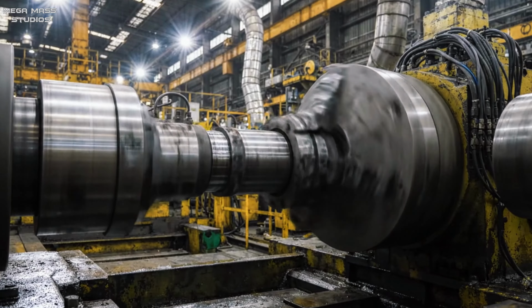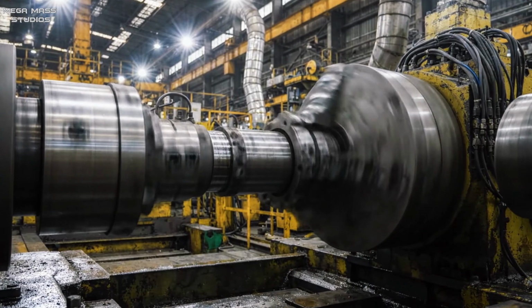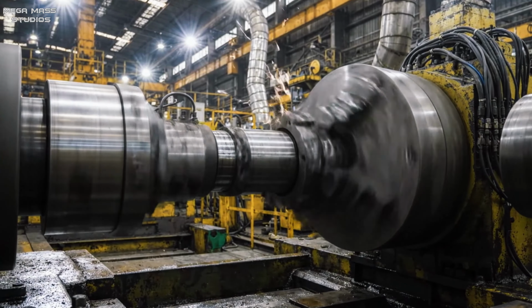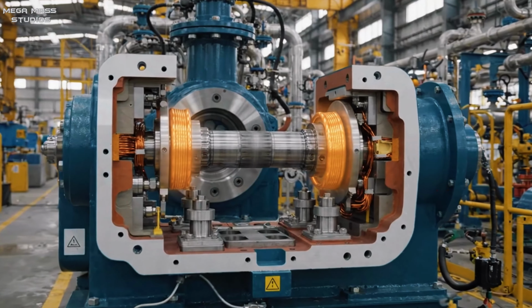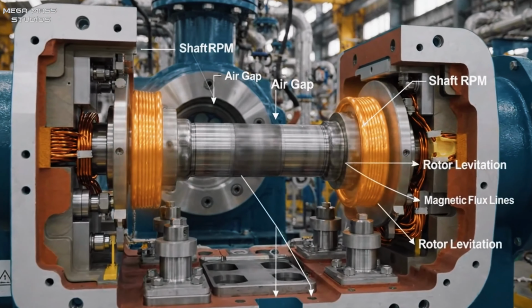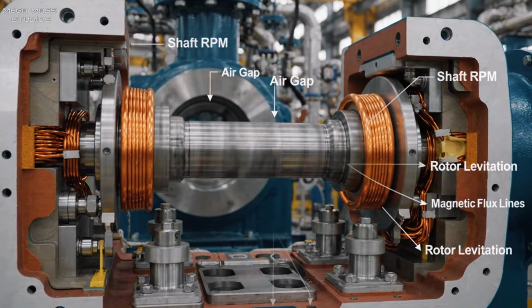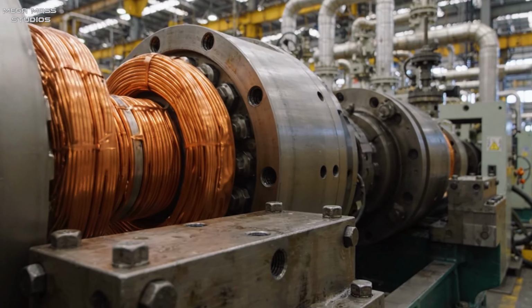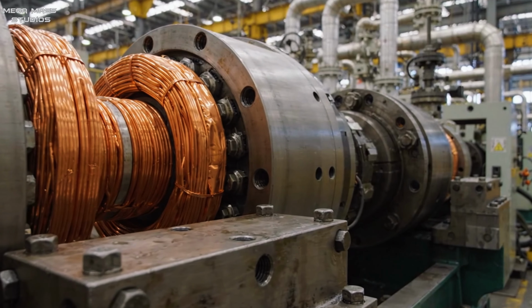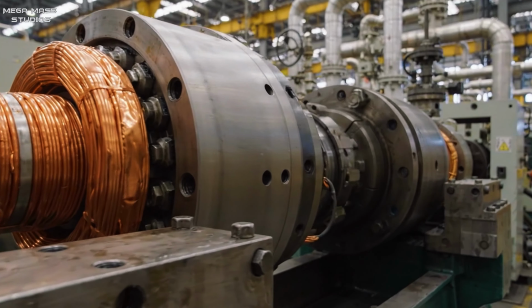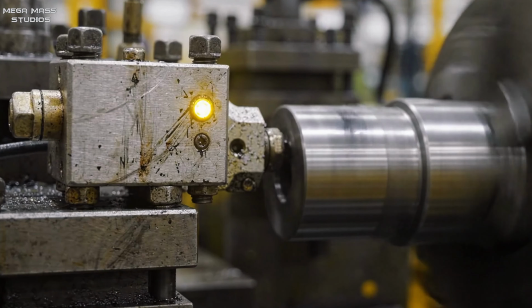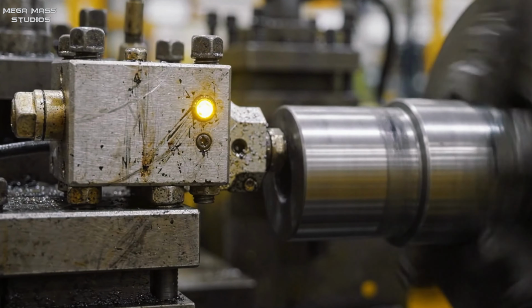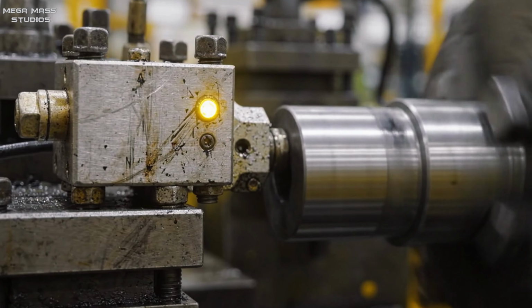This microscopic alignment is critical to prevent dangerous structural imbalance at 3,000 revolutions per minute. The massive rotor shaft is suspended by active magnetic bearings that eliminate mechanical friction entirely. These magnetic bearings use electromagnetic coils to float the heavy steel shaft in mid-air. A dedicated digital controller monitors the shaft position 50,000 times per second using eddy current sensors.